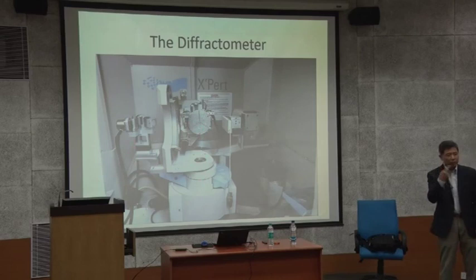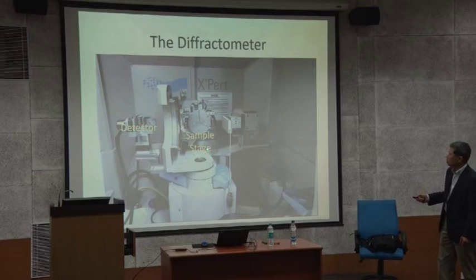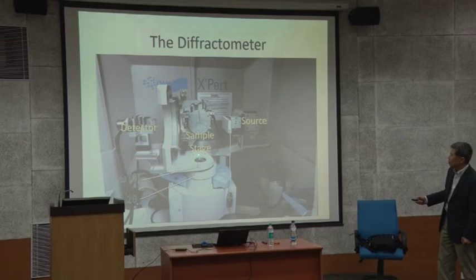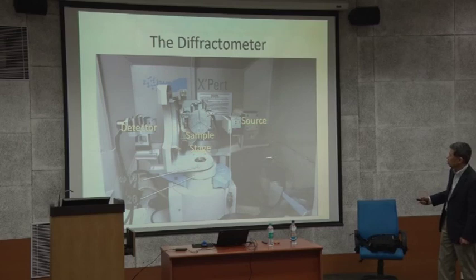And then attached to this one, the sample is attached — this is theta. So you have only two angle motions: a detector and a sample stage. This is an X-ray source. Diffraction happens on the surface. You mount your sample, and then two-theta motion is actually detector motion. Theta is sample stage motion. In the powder diffractometer, you mount the sample on the surface, and the X-ray source comes this way.